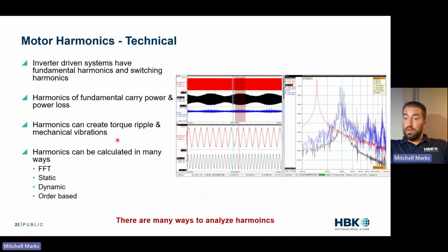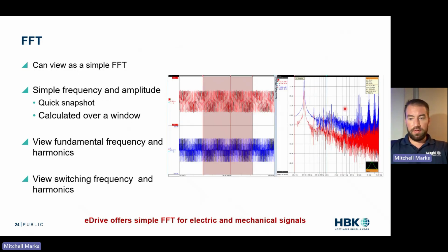Harmonics create torque ripple and mechanical vibrations, so we're seeing a lot of value in measuring those in the same place. And harmonics can be calculated in many ways. FFT, static calculations, dynamic calculations, order-based calculations. If you look into the NVH world, there's 1,000 different ways to look at frequency content. So there are many different ways. And here's an example of a current, a torque, and an accelerometer all measured in one place and then shown as an FFT. And again, this is using our software. You can look at all of these things in one place with one time-aligned stamp. So FFT, I'm going to fly through this.